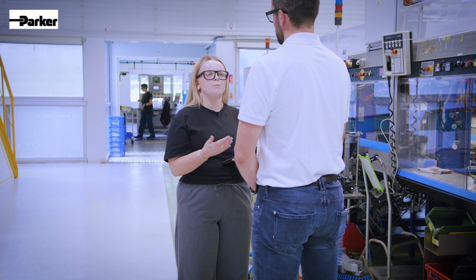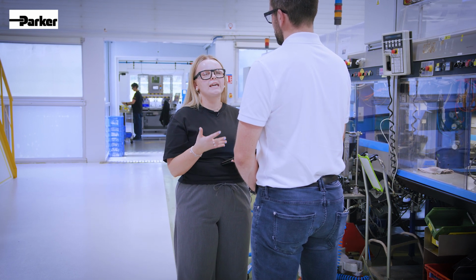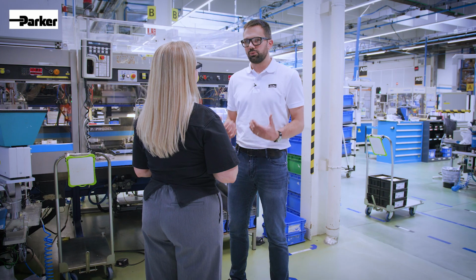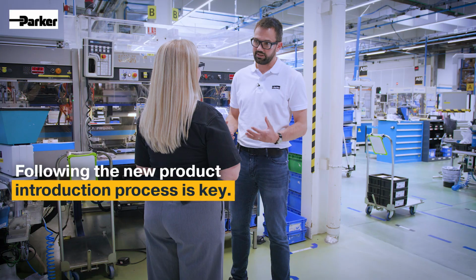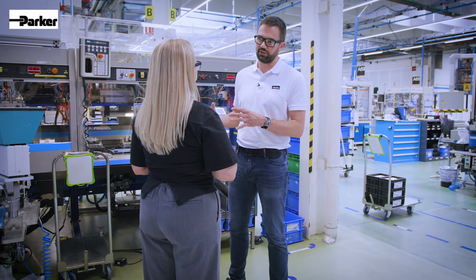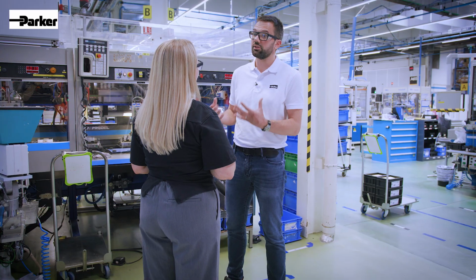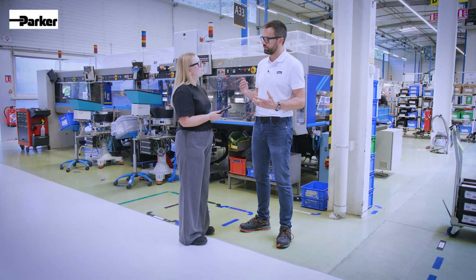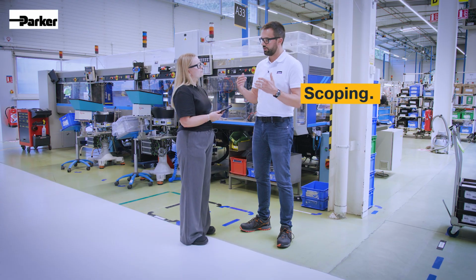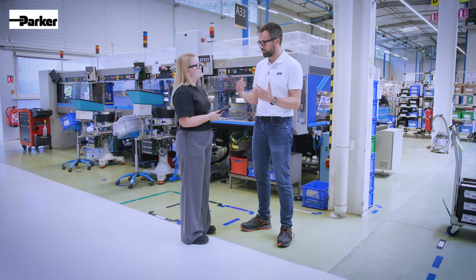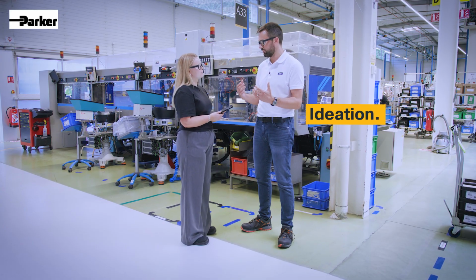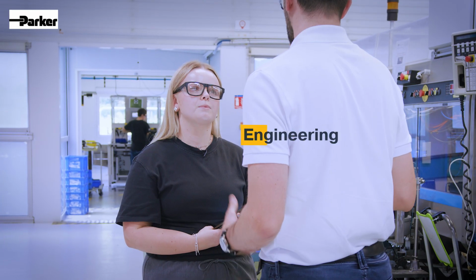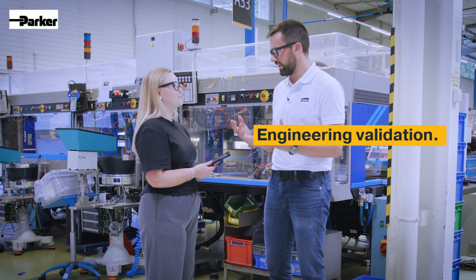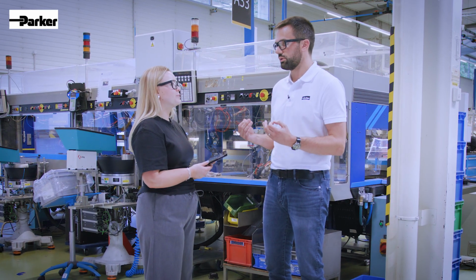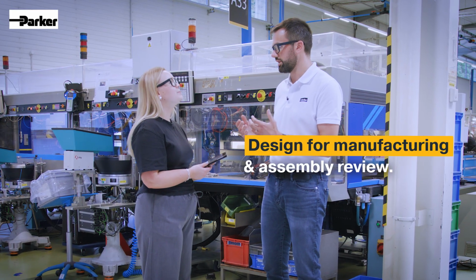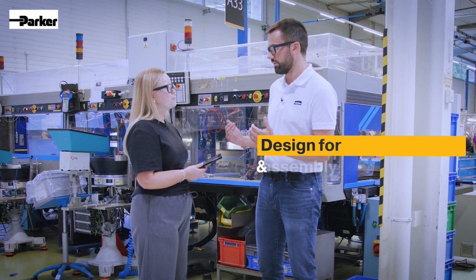When our liquid cooling solutions move from prototype to scalable stage, what are the key considerations we should be thinking about? Following the new product introduction process is the best way to make sure you comply with the specification, quality targets, and lead time. That's a 5-stage process that starts with the scoping phase. During that phase you build the product specification based on application requirements, and you start the ideation phase. Then you have the engineering validation phase, where you evaluate all the engineering aspects of the product, and you start something critical: the design for manufacturing and design for assembly review. That step is really critical, and that's early stage.